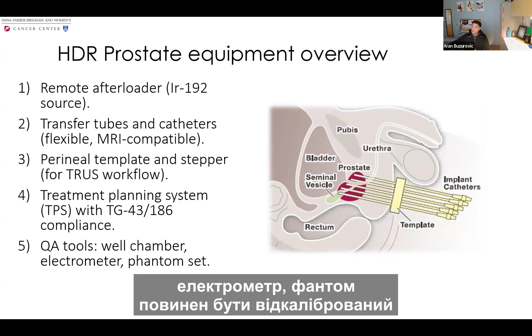In addition to this, quality assurance tools such as well chamber, electrometer, and phantom should be calibrated and ready. This is actually a setup for our HDR intraoperative procedure. We can see a transrectal probe that has two crystals, sagittal and axial. So it means that we can see the images in sagittal and axial.